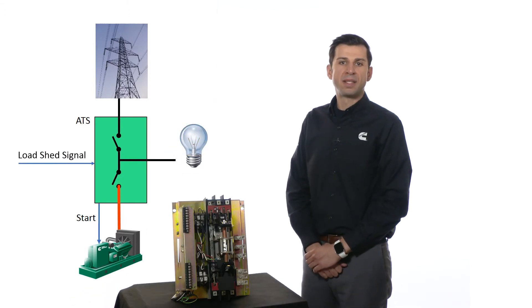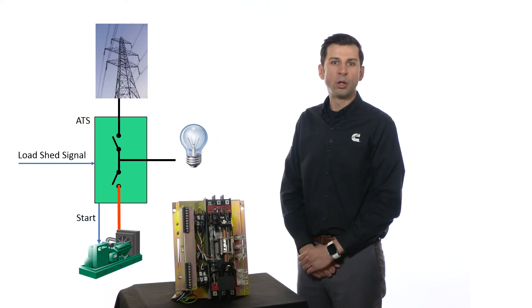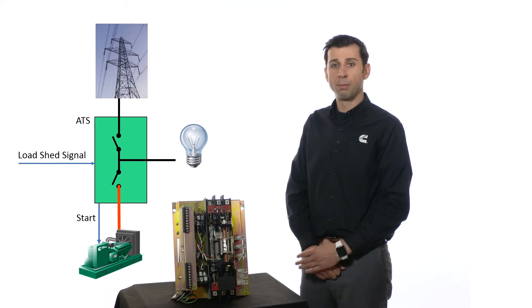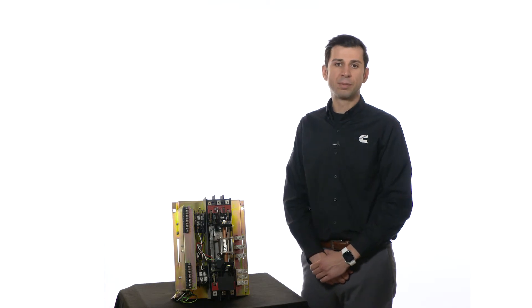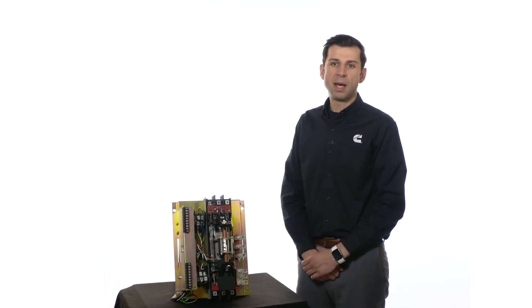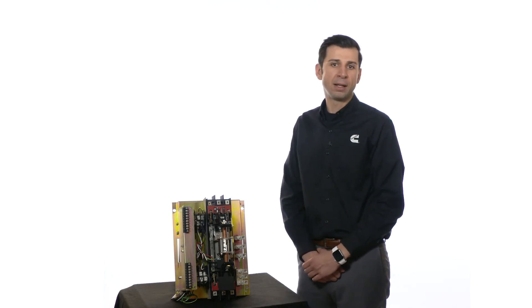The ATS remains in the center-off position until the overload condition is resolved, by an operator for example, and the load shed command is removed. When the load shed command is removed, the ATS moves back to the generator.